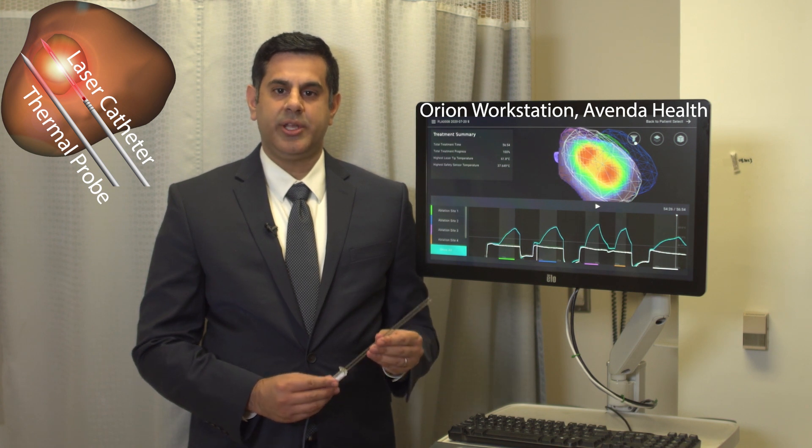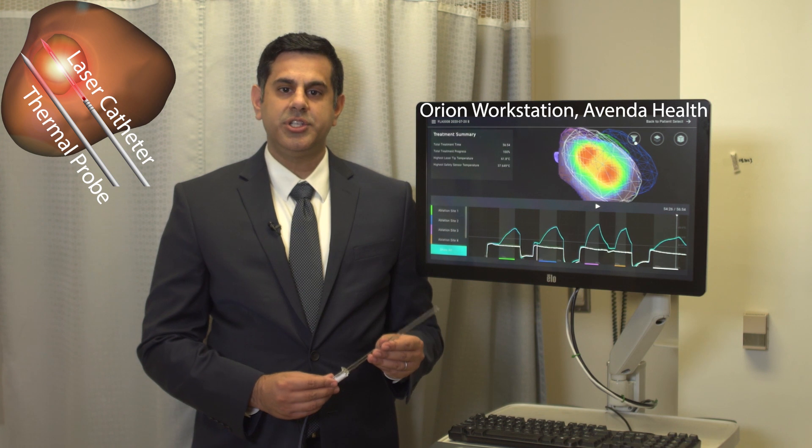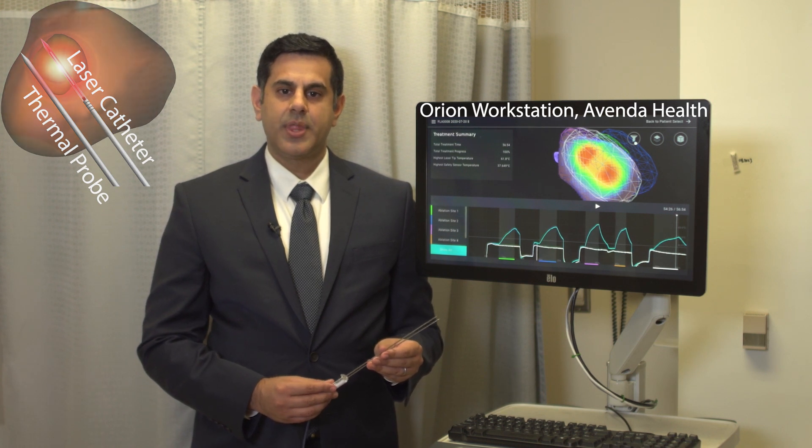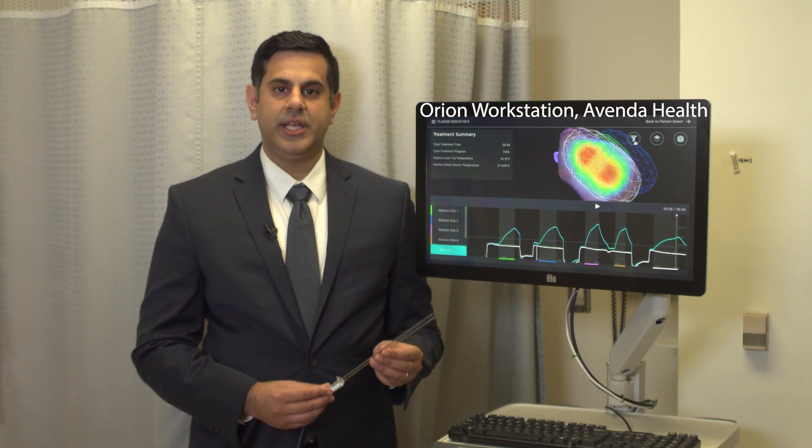Laser heating is controlled during treatment in real time using an interlocking sensor probe, also inserted into the patient. This probe monitors thermal and optical tissue response for safety. If temperatures exceed safety limits, the system automatically shuts off laser heating.